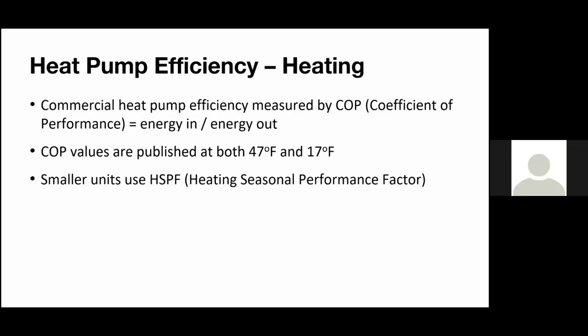But something that's nice to look at, when we're looking at data, AHRI has manufacturers publish and test data for COP values at two temperatures, at 47 degrees Fahrenheit and 17 degrees Fahrenheit. If you don't like those numbers, and you're looking for something a little lower, manufacturers have engineering manuals posted on their websites. So you can go to the engineering manual, and in there, they actually have a chart for both power input along with the different temperatures. So you can actually pull certain COP numbers at specific temperatures if you're looking for just one temperature. And also, if you want to know what that overall average COP in a year is, you can take all that and relate those numbers to bin data, and then you can take an average that way.